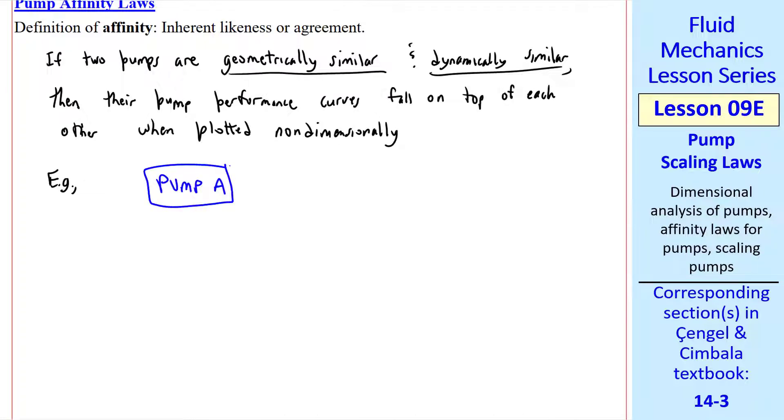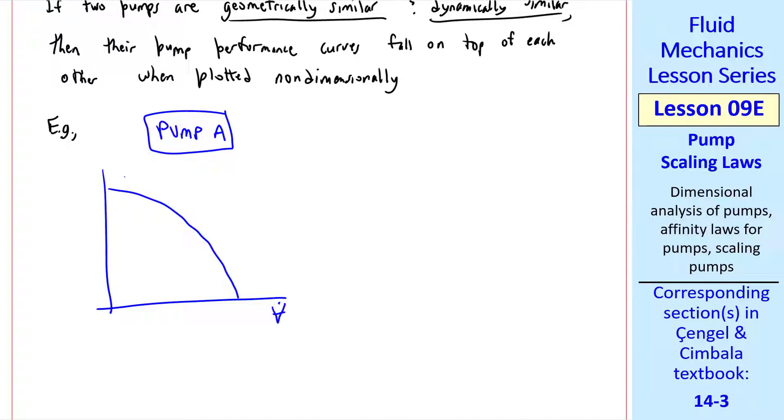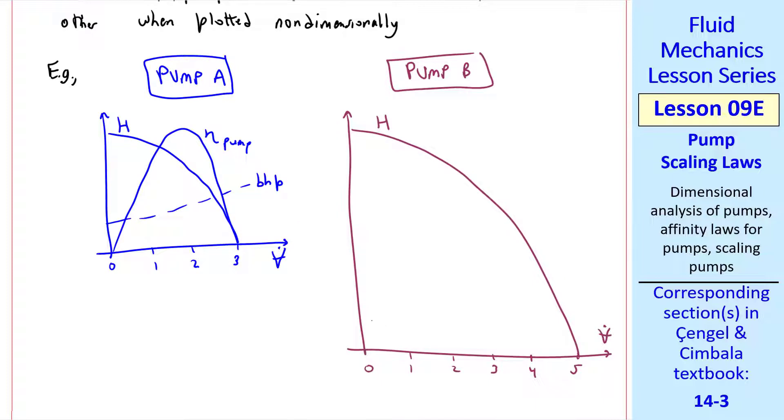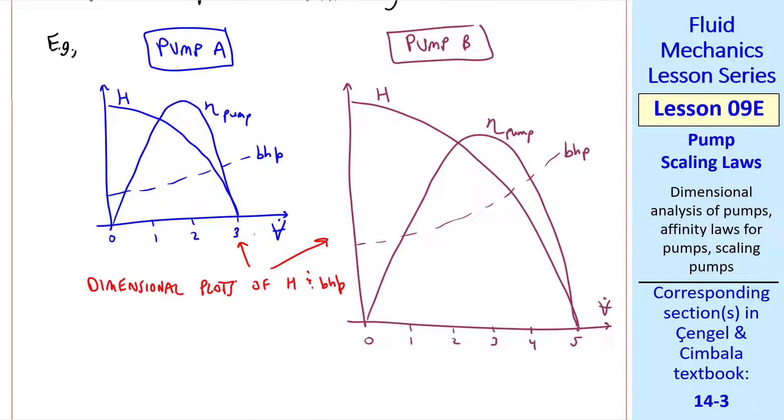I'll use blue for pump A. Suppose its performance curves look like this. This is the net head H, this is the efficiency of the pump, and this is the brake horsepower. Suppose pump B is a bigger, heftier pump, just a scaled up version of pump A. If we plot these on the same scale, in whatever units we're talking about, such as liters per minute, the free delivery of pump A is 3 and the free delivery of pump B is 5. We do likewise with the head and the brake horsepower. So that's the head curve, the BHP curve, and the efficiency curve. These are dimensional plots of H and BHP. Eta pump, of course, is already non-dimensional.